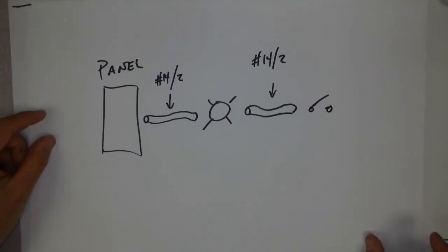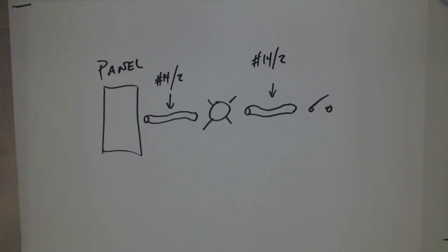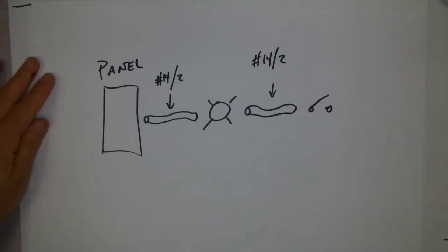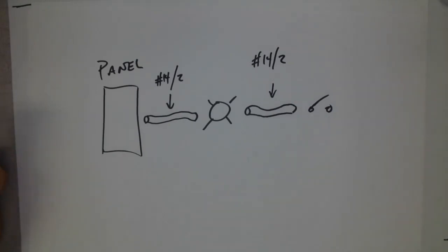4-022 is simply telling you that an identified conductor needs to be brought into every single box and fitting that the main circuit conductors go into. And there was an additional subrule added there. You look at the last subrule of 4-022, and it brings up a very common installation that we would have with cable and lighting. Notice in that new subrule at the very bottom of 4-022, it says, in permanently installed lighting installations, you must have an identified conductor going to the switching outlet.